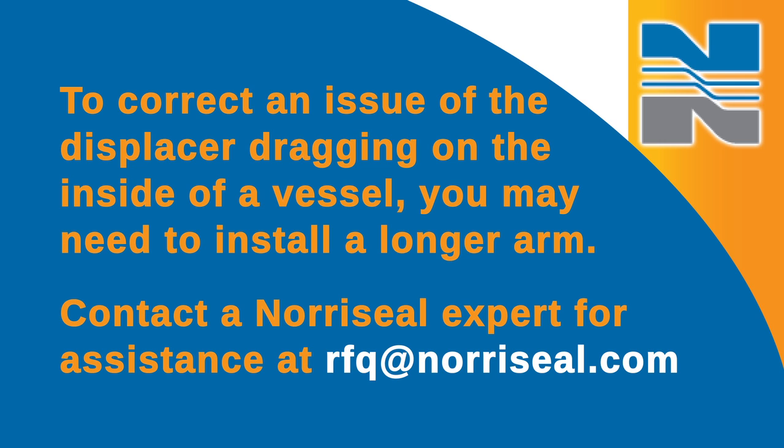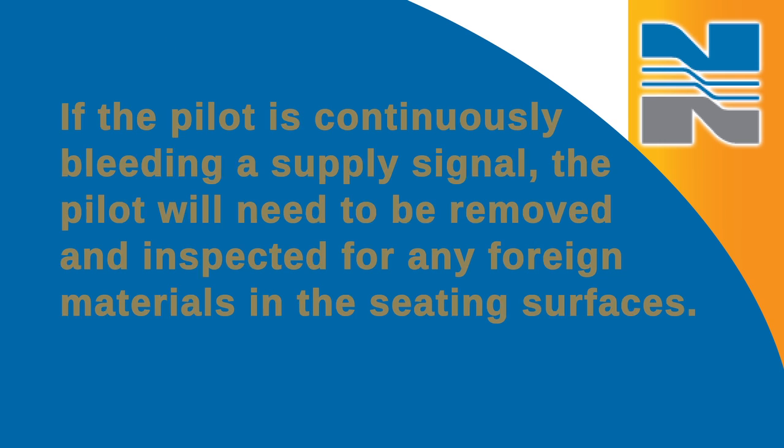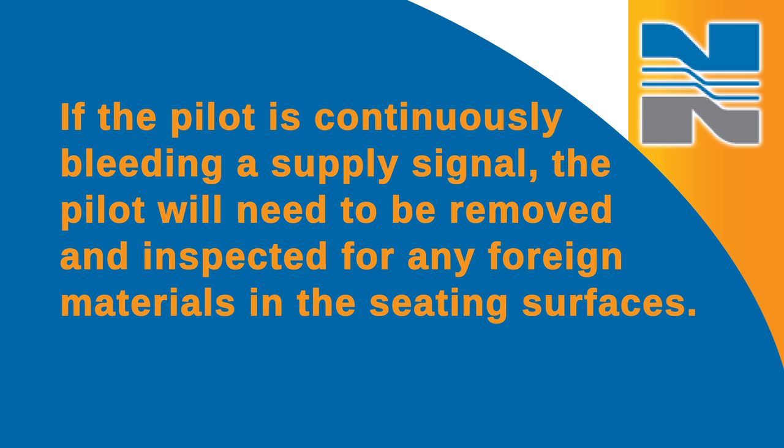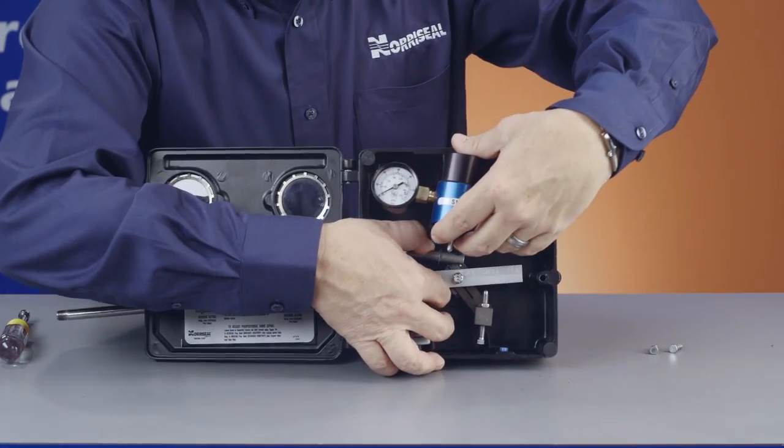Contact the Norriseal expert for assistance at RFQ at norriseal.com. If the pilot is continuously bleeding a supply signal, the pilot will need to be removed and inspected for any foreign materials in the seating surfaces. Make sure you safely remove all air before removing the pilot from the controller. If necessary, replace the pilot.